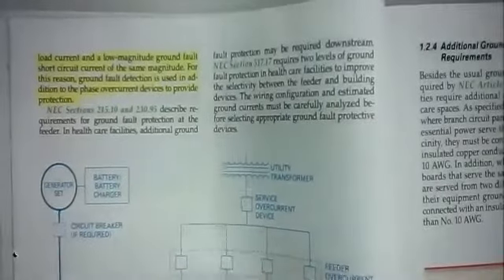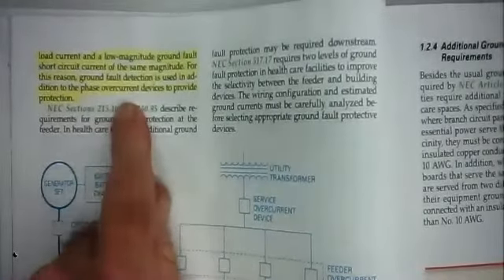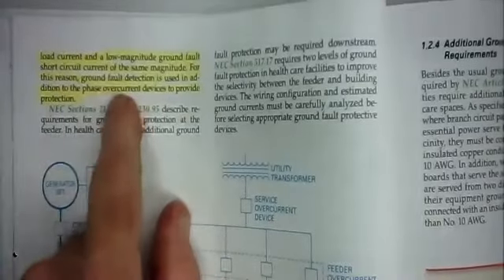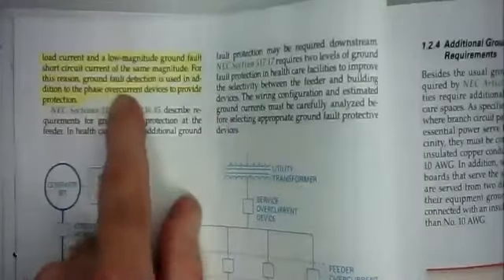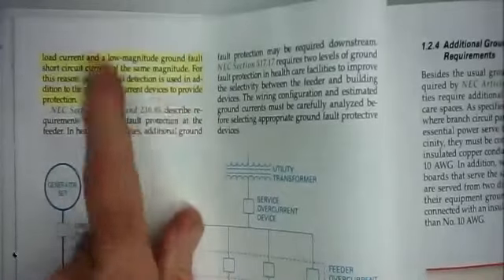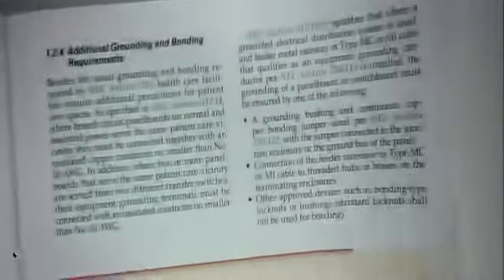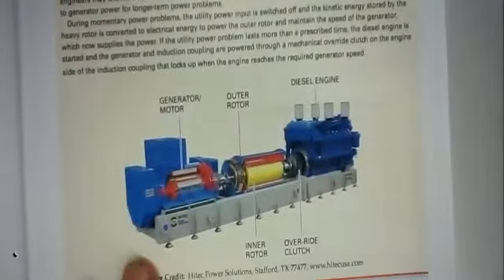Okay. If you have a 20 amp circuit breaker and you've got 15 amps going to ground, that 20 amp circuit breaker doesn't see that as an overcurrent and will not open. But if you have 15 amps going to ground, that's not a good thing. So we're going to have a ground fault circuit interrupter. This is not highlighted, but it's very interesting.